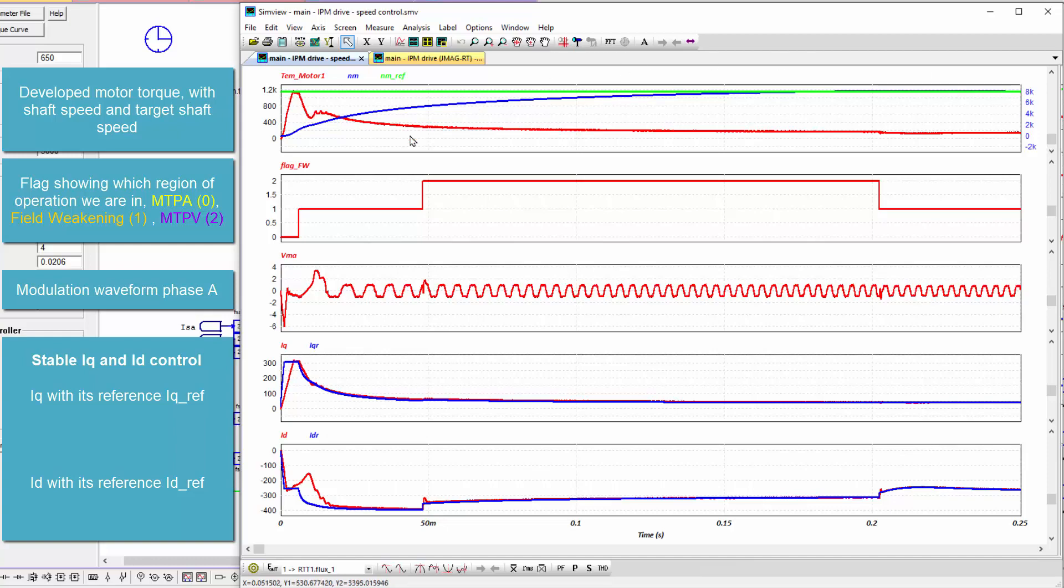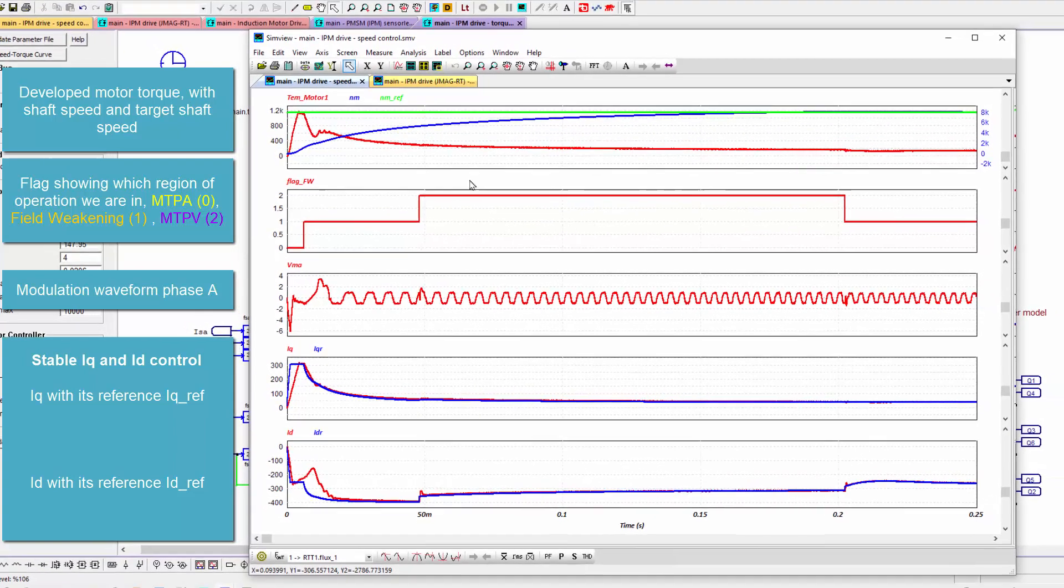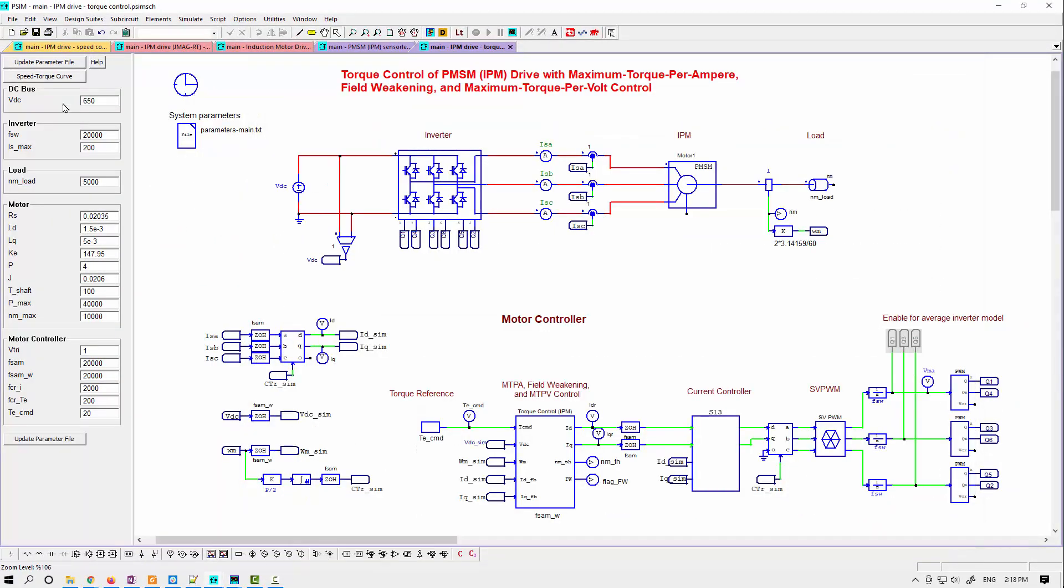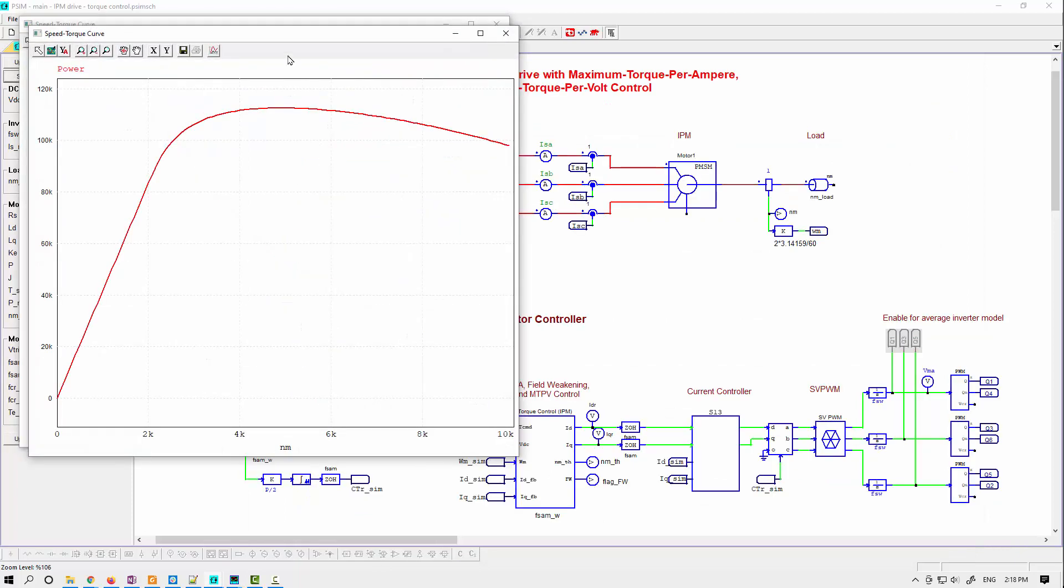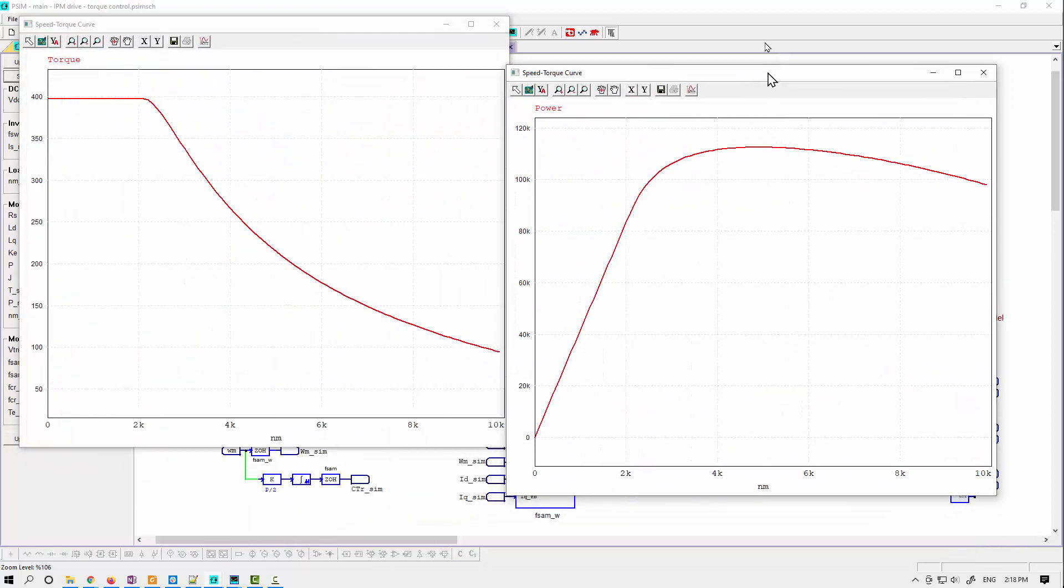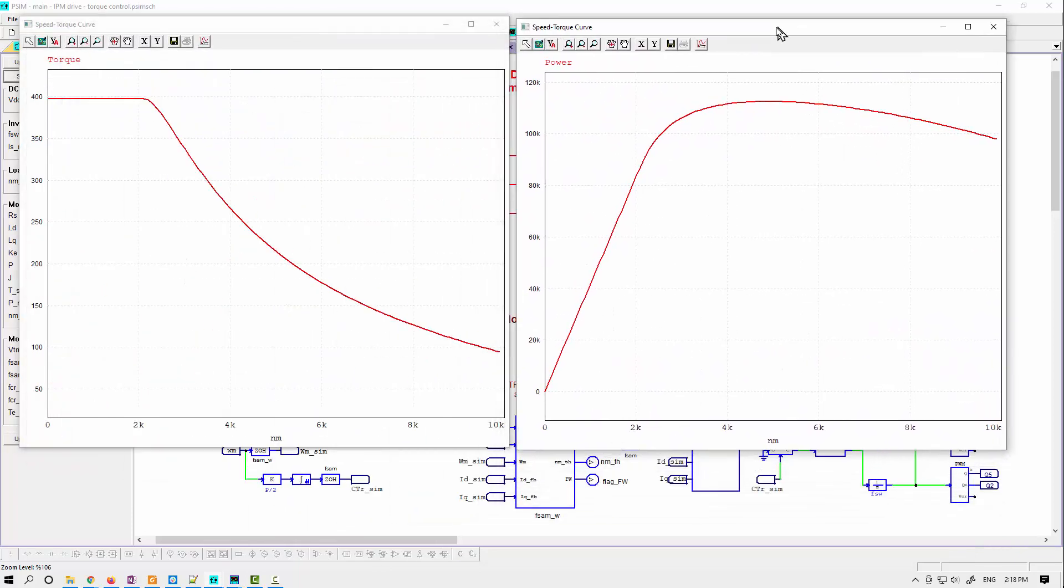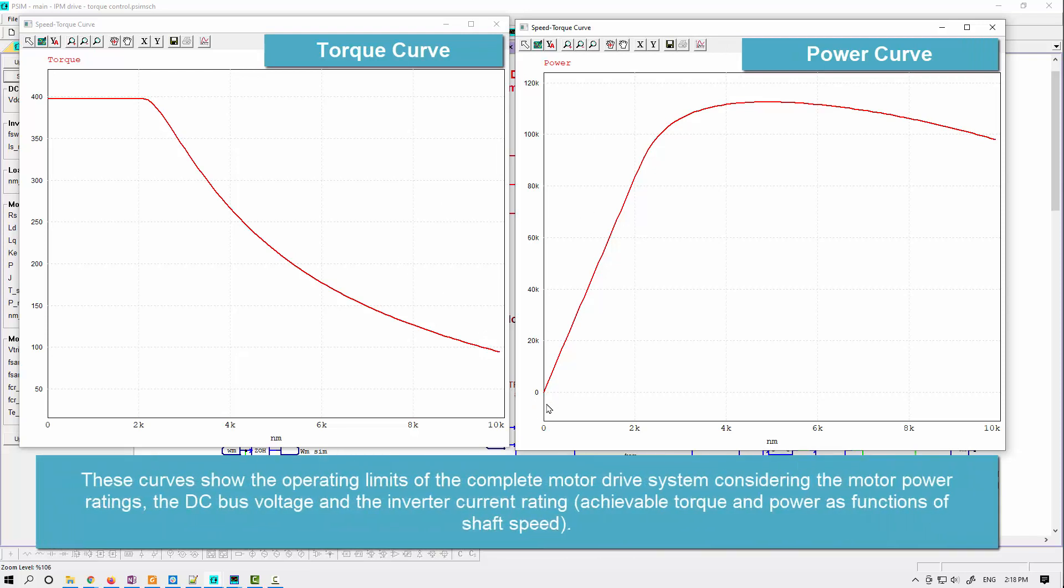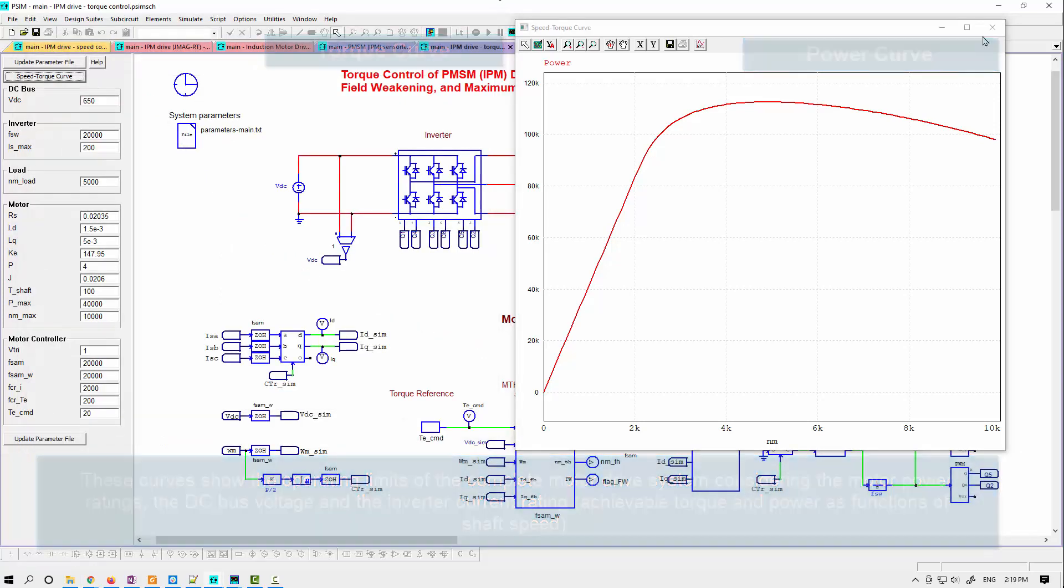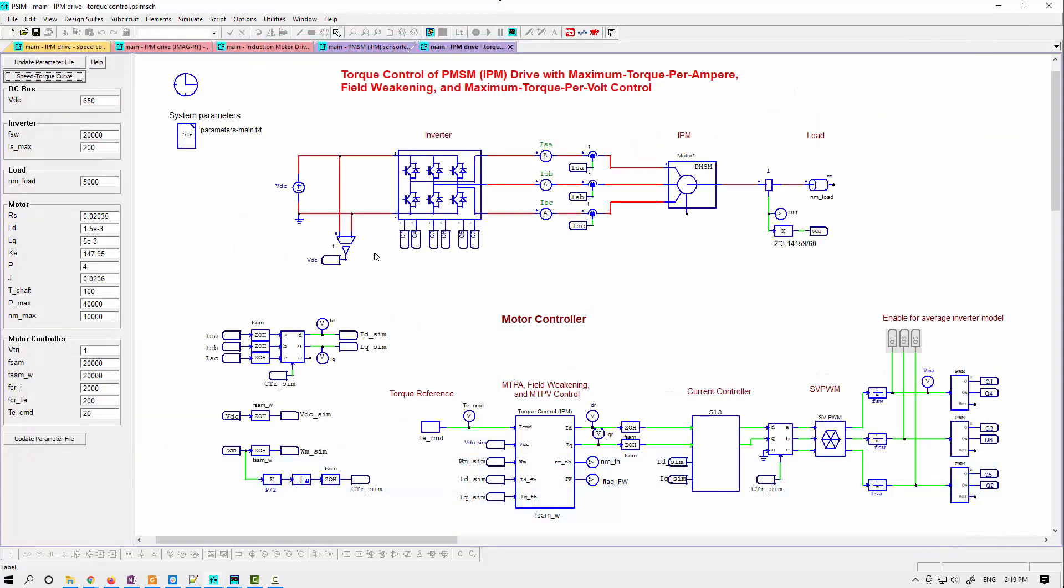You could also look at what the torque and speed curves and power curves will look like. If you push that button, it will calculate for you the power envelope here as a function of shaft speed. And we'll also see the torque possible as a function of shaft speed. This is, of course, with max torque per volt control, field weakening, and max torque per ampere control included. So that's one of the changes we've done.